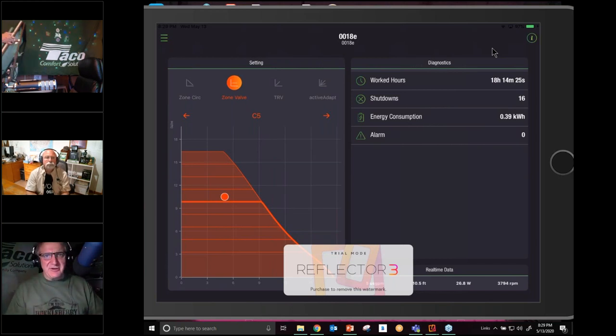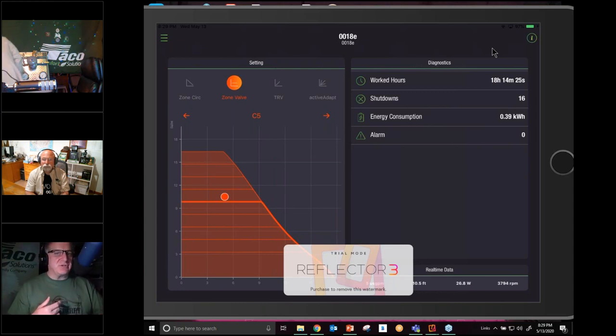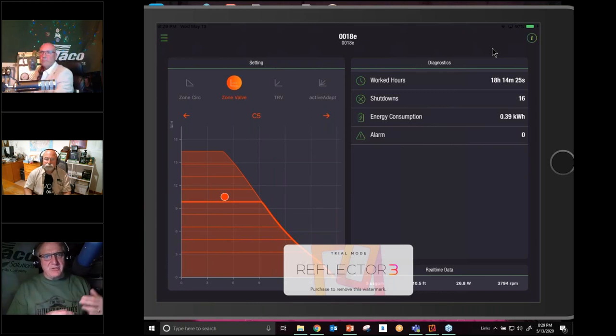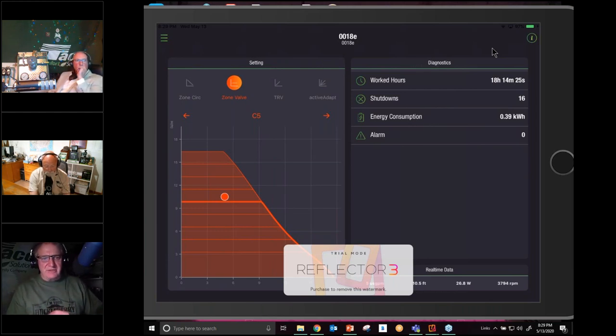If you put a high head circulator on the return side, like your standard three-speed pump, it's a low-flow, high-head, steep-curve pump. You put that on the return side in place of a circulator that was a higher-flow, lower-head, flatter-curve pump. You're changing the dynamics of the system, and you're going to create problems that weren't necessarily there before. So if you're going to replace a dead pump on the return side, make sure you replace it with a pump whose performance characteristics are pretty similar to the one you've taken out. A typical flat curve pump like a 007 is going to make a lot more sense than a steep curve pump like your three-speed pump, like the TACO 0015 standard efficiency or the Grundfos 1558. They just don't make sense there. So that's the way I would look at that for pump location.